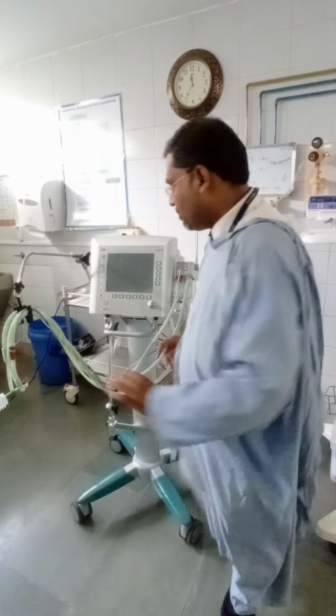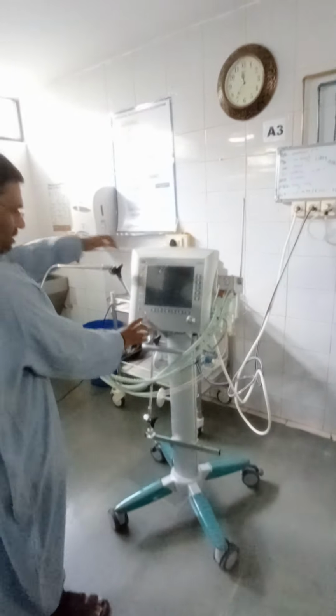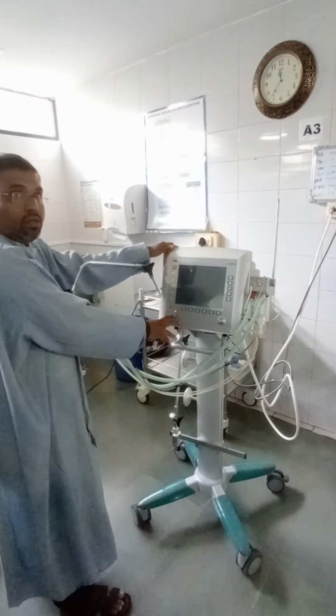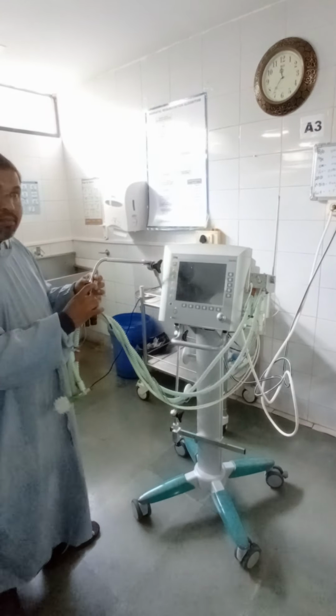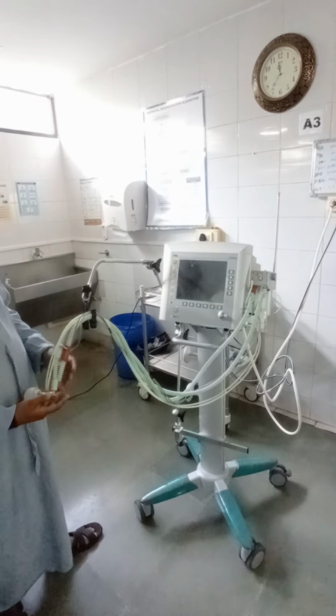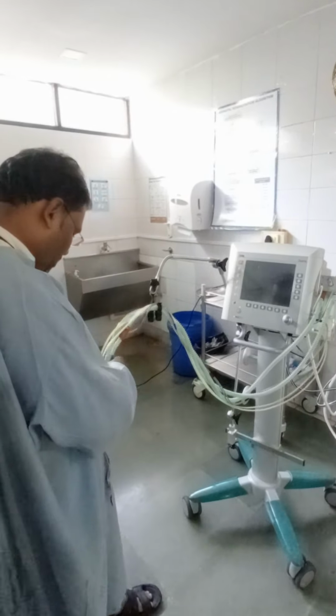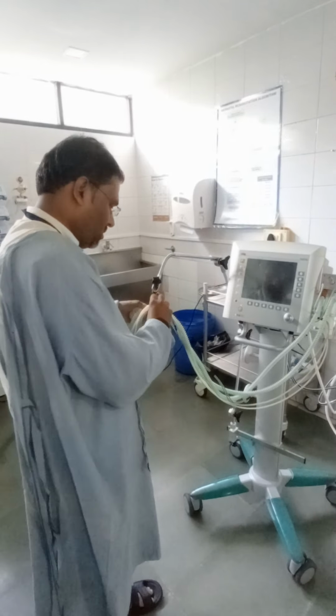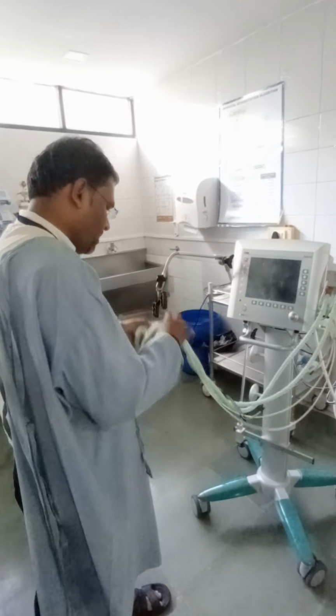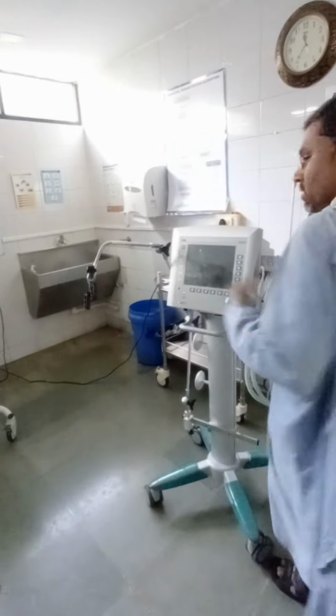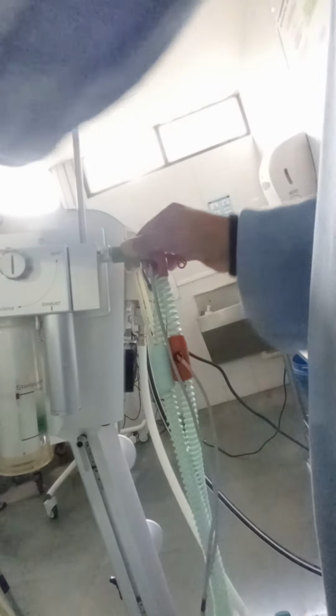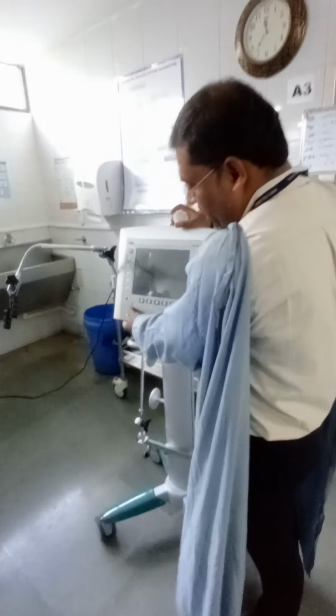Now we are going to start the machine. See, this is a switch, right? Before starting the machine, what you have to do? You have to just make the flow sensor calibration, right? Don't connect the test line directly. Come close. This is a slot which is given here. You just connect it like this. Okay? Then you just switch on the machine. So what will happen? It will do flow calibration automatically.